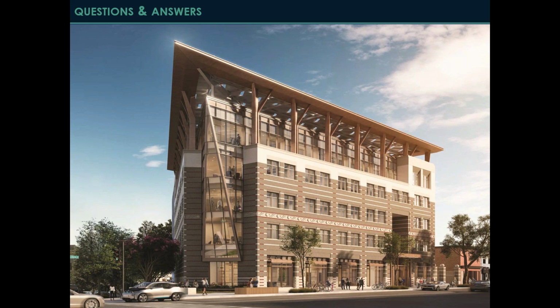Next question: what percentage of savings can be achieved with radiant ceiling systems? When we compare and contrast, we often use a VAV system as the baseline in Washington, D.C. Other systems such as DOAS-FCU systems or chilled beam systems can reduce energy by 10, 15, 20%, but we've seen savings up to 35% on the energy model using a radiant ceiling system.